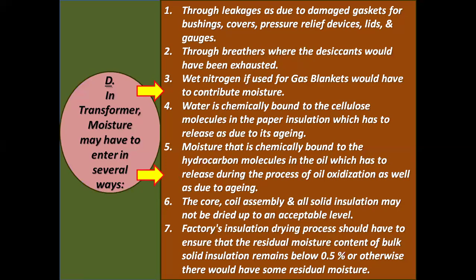Number D. In a transformer, moisture may enter in several ways. One, through leakages due to damaged gaskets for bushings, covers, pressure relief devices, lids, and gauges. Number two, through breathers where the desiccants have been exhausted. Number three, wet nitrogen, if used for gas blankets, can contribute moisture.